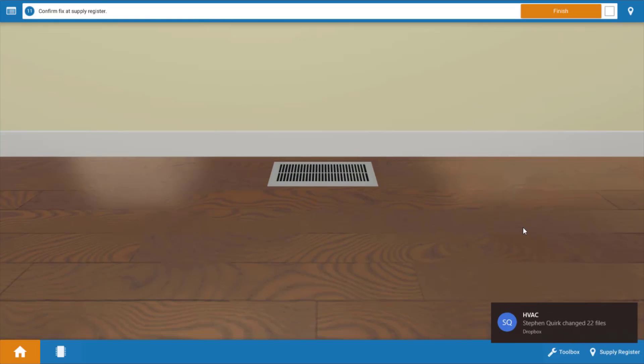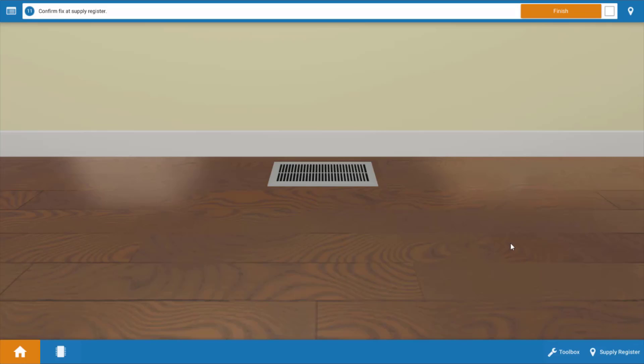This should cause the pressure switch to now close and again it may be necessary to reboot the furnace. We want to go up to the house and verify that heat is reaching the space and if we look at the floor register here we can see that we do in fact have heated air coming out of the register. So we've solved the problem.